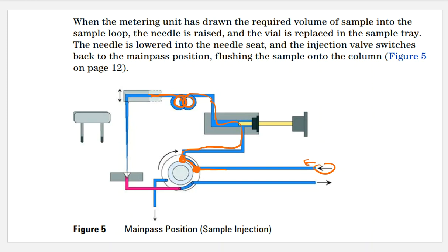And then that mobile phase continues to go through, and it goes through the needle to kind of rinse all of that out too at the same time. And then it goes through the needle seat. And when it goes through the needle seat, it goes into spot number 5, and then it makes its way to spot number 6, where then it goes out. Folks, the mobile phase flushes the entire chambers, analytical heads and all of the tubing lines that held your sample.